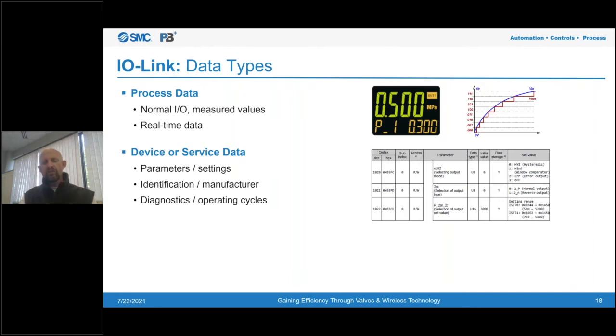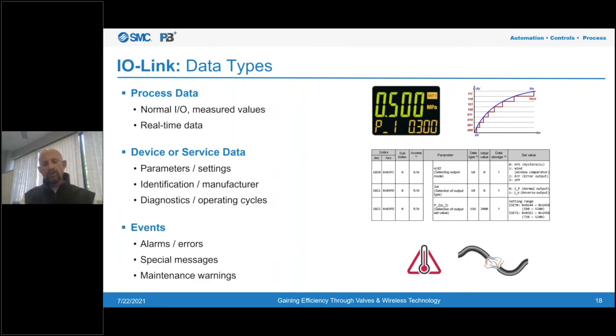But in addition, outside of what traditional IO is able to bring to the table, IOLink also collects and stores device and service data. This includes parameters and settings for devices, as well as device-specific information like model number and manufacturer. It also keeps track of diagnostics on devices, such as operating cycle rates, and keeps track of alarms and events. Any maintenance warnings or special messages are communicated back and forth between an IOLink master and an IOLink device.